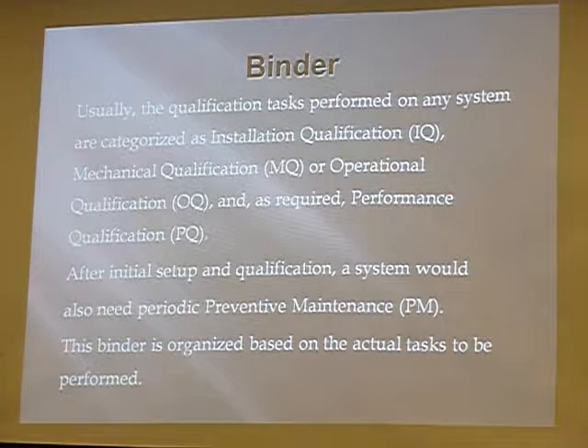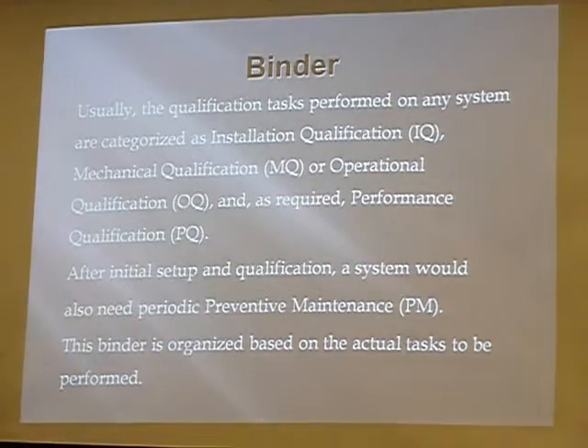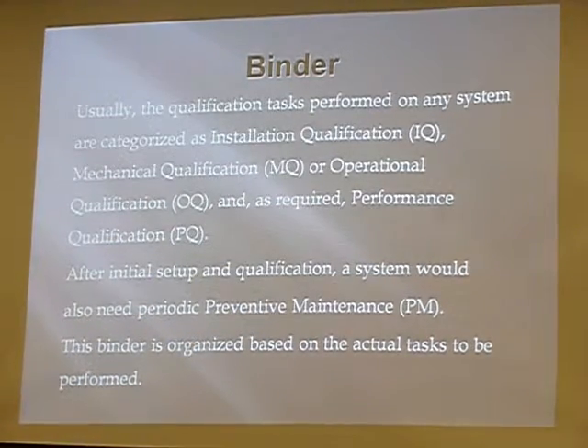We changed it because there were some labs here in the United States that were complaining that inside their USP, the way it's written, the OQ that we used to perform wasn't encapsulated, it didn't say MQ. And it calls for you performing an MQ in the USP documents. So we changed our verbiage on how we do things with the baths, and we decided to call the acronym an MQ, mechanical qualification, which is what it is. You're doing a mechanical qualification, making sure the mechanical aspects of it are good, and then we do a PQ, performance qualification, which is the performance verification test. That's the chemical test. So we do a mechanical test, and we do a chemical test, a performance test.